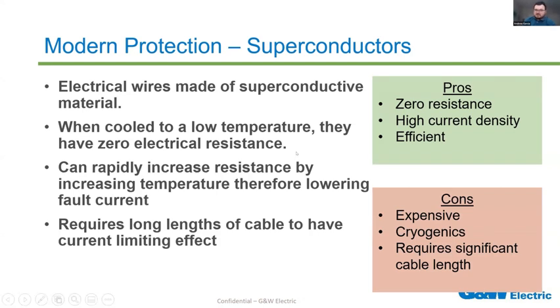That means that your workers are going to have to be trained and equipped to deal with cryogenic hazards, because in order to reach that extremely low temperature, you are going to need to pump cryogenic fluid, such as liquid nitrogen, through these conductors. And once again, it does require a significant cable length in order to have any kind of current limiting effect. As a matter of fact, a short run of cable would probably have the opposite effect, and end up increasing the overall amount of fault current by lowering the overall resistance in that conductor path.